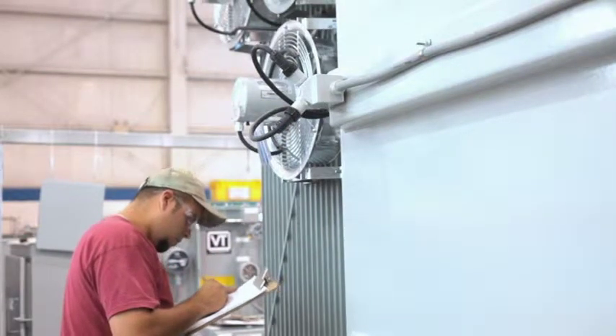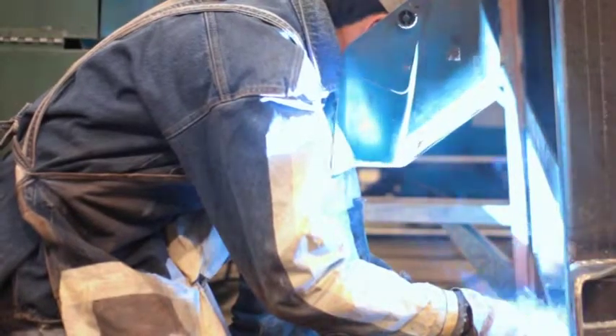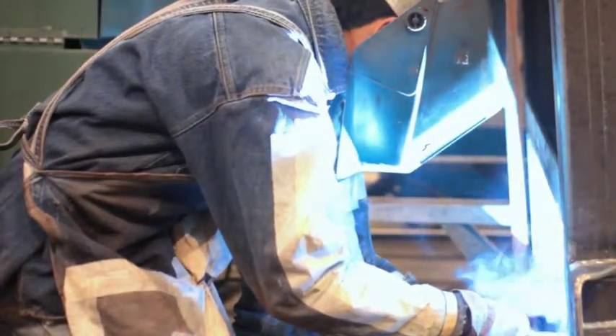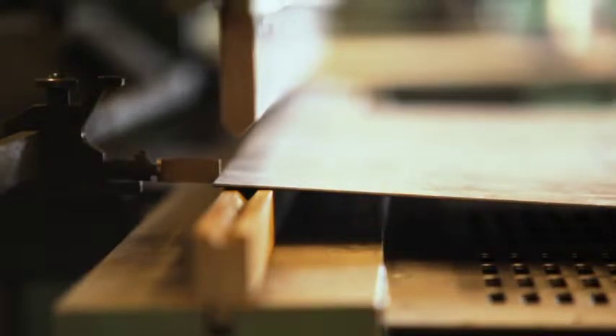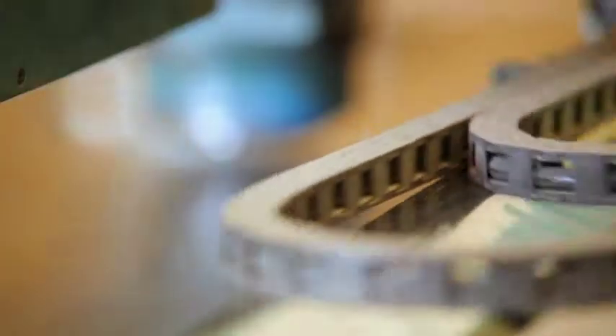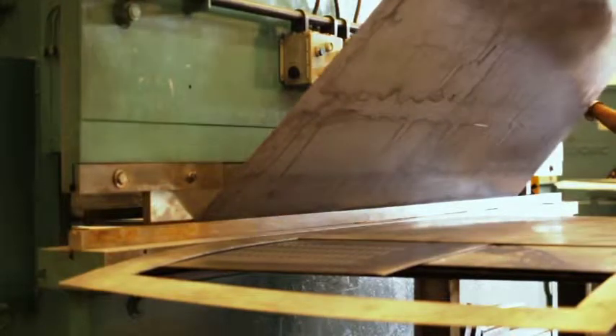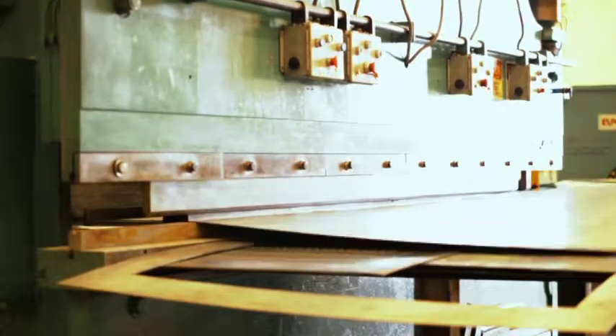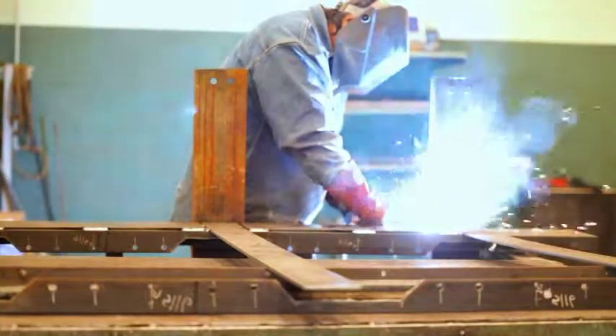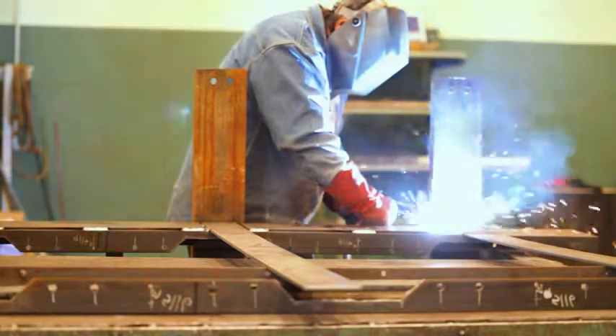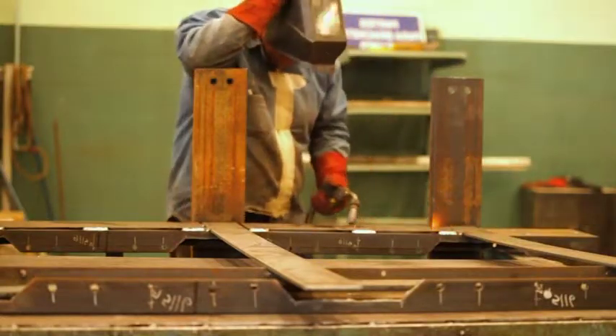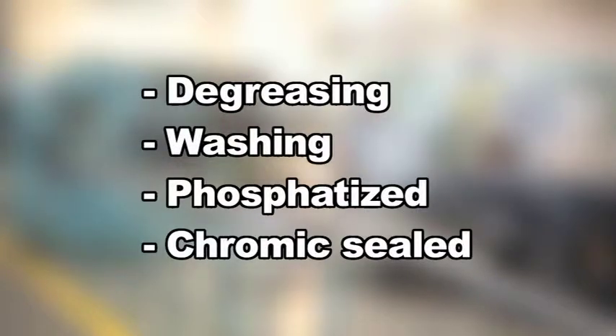On the other side, for the dry type transformers line, the first task is to make the necessary cuts in the steel sheets. To do this, precise cutting machines are used, then the sheets are passed to a CNC punch press that ensures the accuracy and quality of the holes required. After this, they go to a bending stage with high capacity and accuracy CNC benders. The pieces are sent to a minor welding stage for joints, which is done by highly qualified and certified personnel. After the welding, the panels move to a different stage in order to proceed with the degreasing, washing, phosphatizing, and chromic sealing, which ensures an excellent anchor for the painting.